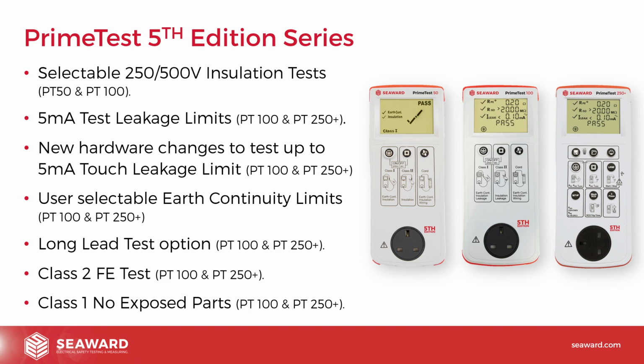So first, let's have a look at what we've done to the Prime Test range of products for the 5th edition. To start with, for the Prime Test 50 and the Prime Test 100, we've added the ability to test at 250 volts. Previously you could only test at 500 volts, which meant if you wanted to test surge protected equipment or very sensitive equipment, for example, you were stuck because you didn't have an option to do that. Obviously most equipment would be fine at 500 volts, but giving you the option to test at 250 volts is a nice additional feature. The way we've done it with the Prime Test 50 is that it will default to 250 volts. So 250 volts is the default setting.